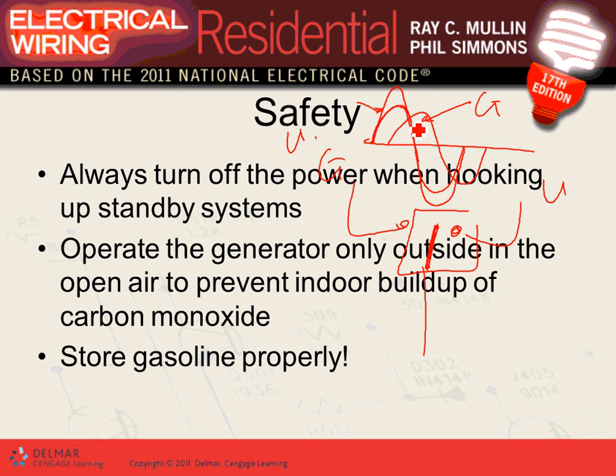Okay, operate. So when hooking up the standby generator, turn off the power. The most important thing is to turn off the power, right? But you don't just turn off the power. Legally and based on the code, they don't just turn the switch on and off. They have to have a mechanical interlock. If you forgot to turn off the power, what's going to happen? You're going to blow up your generator. So what they want you to do is have a mechanical interlock, and you'll see how. As you turn the utility on, the switch of the generator is off, and vice versa. So you can't turn them both on at the same time, even if you want to.